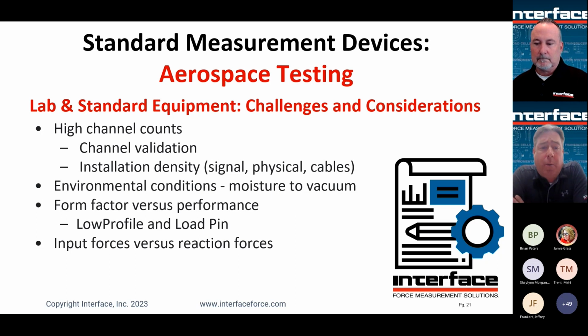Load pins have been one of the devices that have been more common in higher force applications in most recent years. Load pins are essentially a circular device designed to fit inside of an existing structure, and the dimensions or form factor of the load pin actually drives the performance. So the trade-off there is you get potentially a much more dense measurement, where you can have more actuators in a small space and potentially greater peak forces at a small size, but you wouldn't have the performance of a low profile load cell. So some trade-offs there. But typically what we've been seeing is that as those force magnitudes get higher, the measurement resolution or accuracy requirements tend to decrease a little bit.